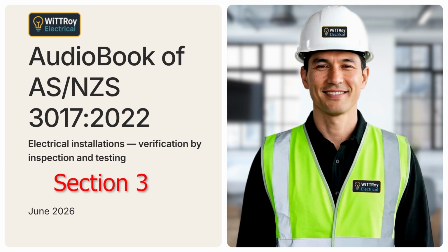Clause 3.1 General. Clause 3.1 explains when visual inspection is required. A visual inspection must be done when work on an electrical installation has been completed. The purpose is to verify that the work complies with the applicable requirements. In simple terms, after electrical work is finished, we do not just energize it straight away. We first inspect the work to check whether it looks correct, safe, and complete. The visual inspection must be carried out before testing or at the same time as testing. Where practicable, the visual inspection should be completed before that part of the installation is placed in service.